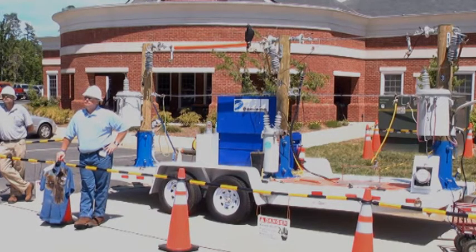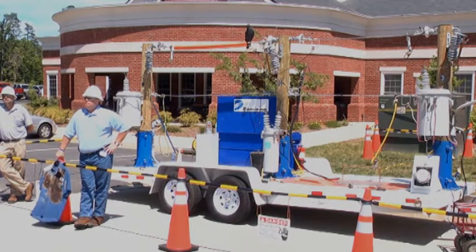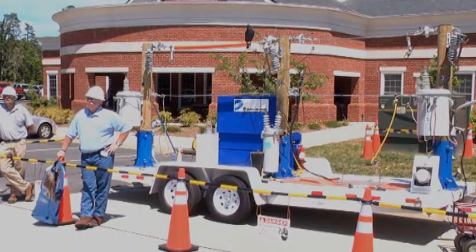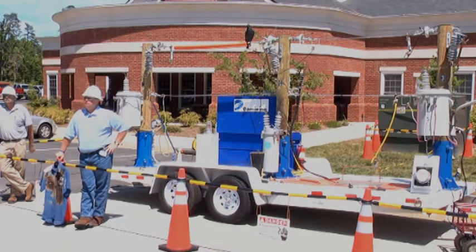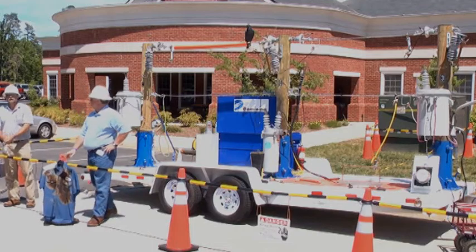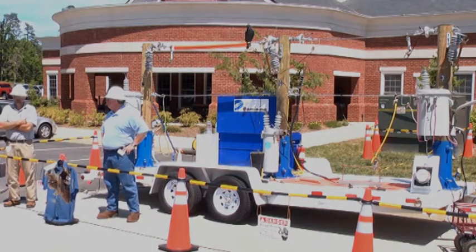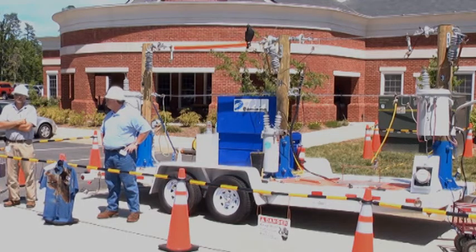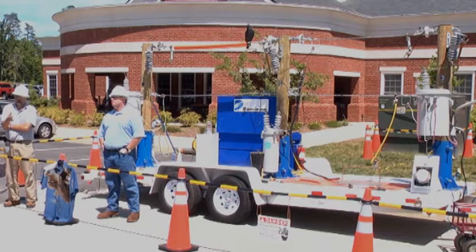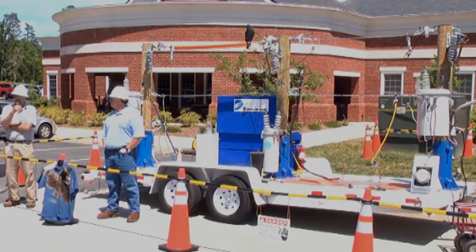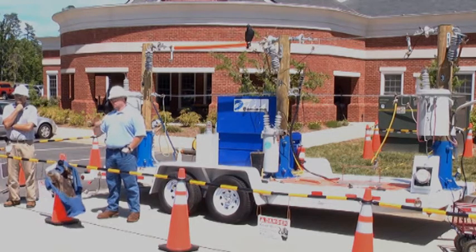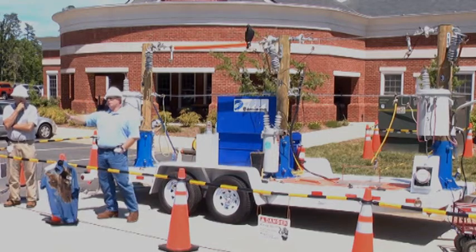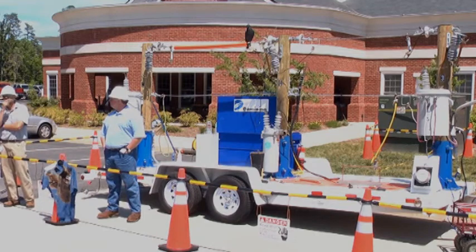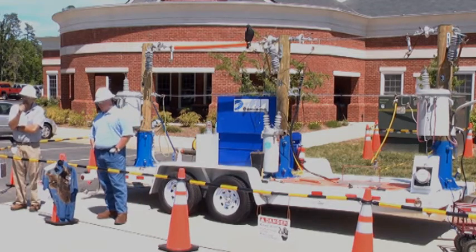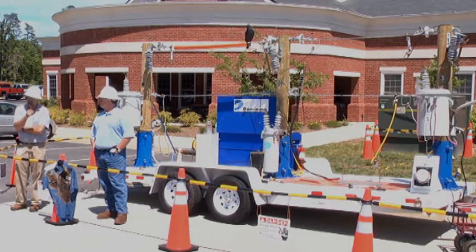So what if we're on a house fire and, like my volunteer company, they'll still pull the meter — now you're not supposed to, but they'll do it — so we're in there fighting fire. What's the likelihood of having charge still in that house? We recommend that you don't pull the meter, and let us come out and pull it to keep you safe. We've had instances where primary got into the house, into the secondaries, during ice storms and thunderstorms. We just had that in a vehicle accident where the pole came over and the primary got onto the service drop going to the house. What you just saw on that meter base — within one eighth of a second, you can generate up to 6,000 amps of fault current.